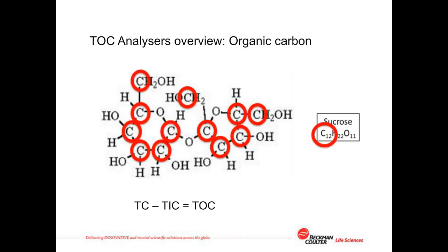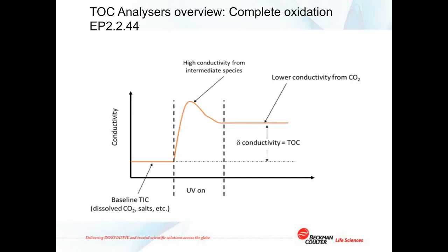A pharmaceutical grade TOC analyzer uses ultraviolet light to oxidize the organic molecules present in the water to release the carbon atoms, and then measures the difference in water conductivity caused by the resultant carbon dioxide. TOC is calculated according to the pharmacopoeias by measuring total inorganic carbon and total carbon, then subtracting one from the other: TC minus TIC equals TOC. The European Pharmacopoeia chapter 2.2.44 on TOC analysis emphasizes the importance of complete oxidation of the organic contamination in order to release all carbon atoms and get an accurate TOC measurement.